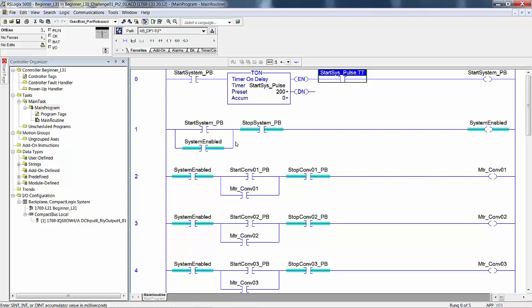Don't forget to set the stop push button bits to 1 on before you test any of your simulation code. Those bits are always in the on state when the push buttons are at rest, not pressed against the spring return. That's what at rest means, that you're not depressing the spring, it's at rest. Just the opposite of the start push buttons, the stop push buttons are normally closed. Operating them is to momentarily open the contacts. When you toggle the stop push button off, the on-delay timer is going to do the exact opposite thing that it accomplished with this rung.